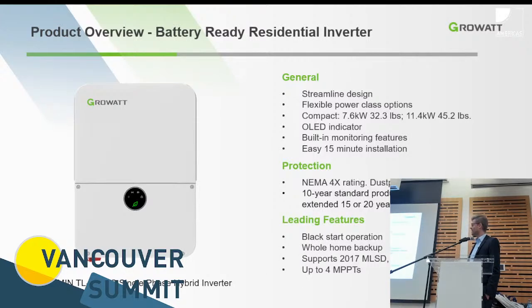Some of the features that are relatively unique is that the inverter has a very high peak current capability that is relatively rare for a transformer-less inverter. Because normally in the off-grid day and age, like a Schneider XW Pro, you had an output transformer, and the output transformer plus, of course, the power stage allowed for extremely high peak current that you can drive a sump pump or start a motor or compressor off your fridge or something like that. But this system, even though not having a transformer on the output, still has a very, very high inrush capability to start your home if the system is completely off, for example.